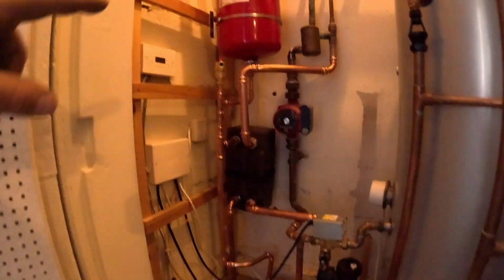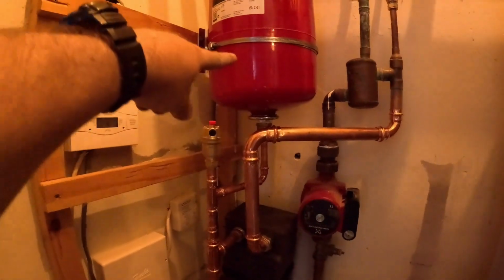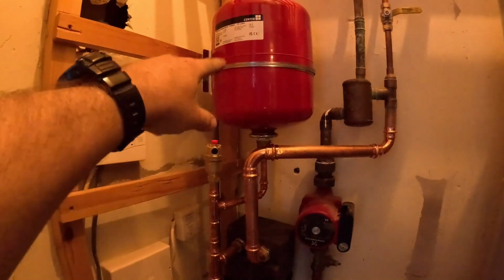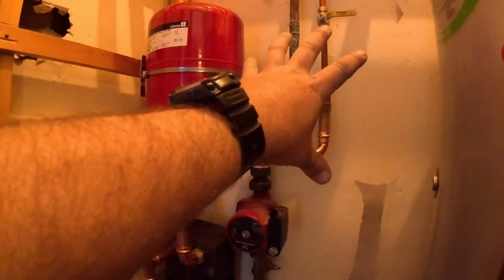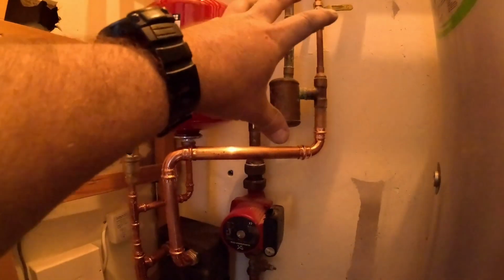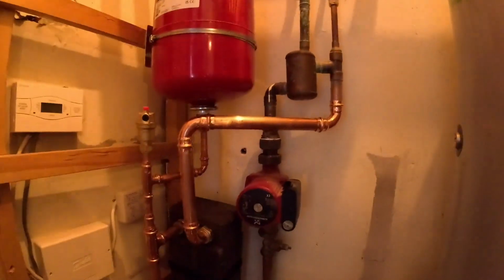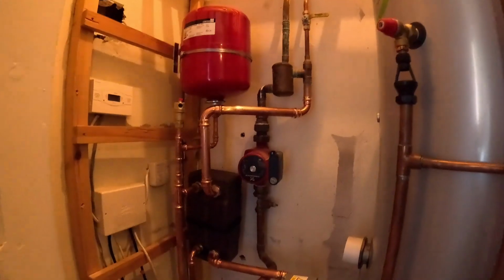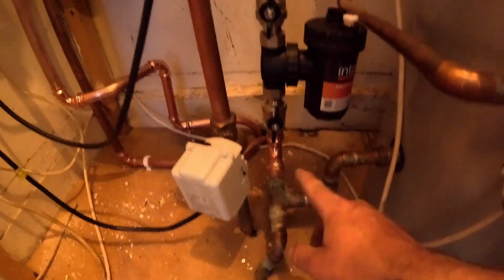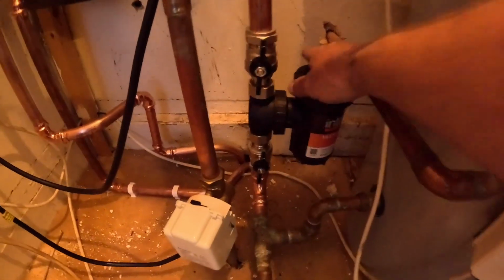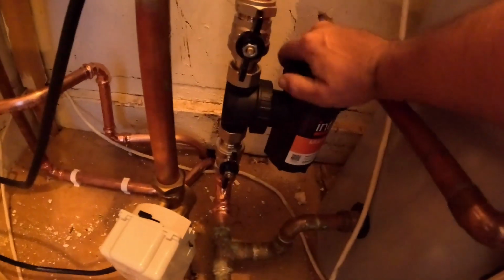This is the airing cupboard part. We've got the expansion vessel here for the sealed part of the system, the new boiler side. The old side stays on open vent so we don't have to break into that and cause any issues. All we've come out of is the return from the cylinder and the heating straight into a heat pump rated inline filter.